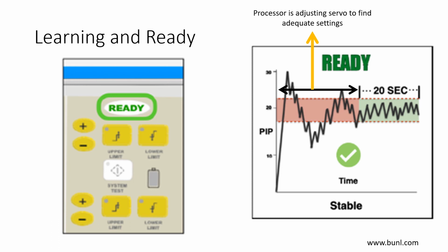In the learning mode, the internal processors are performing calculations and adjusting the servo pressure to achieve the desired settings. While in the learning mode, no alarms are active. Instead, they are being calculated and will be set when ready. When the ventilator transitions from standby, the monitored values will adjust almost sporadically. However, these variations should not alarm the provider as the servo is just fluctuating as it attempts to achieve the desired settings. Once the pressure has stabilized for 20 seconds, the ready light will turn on.